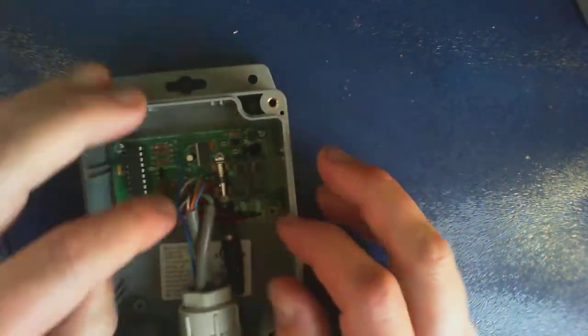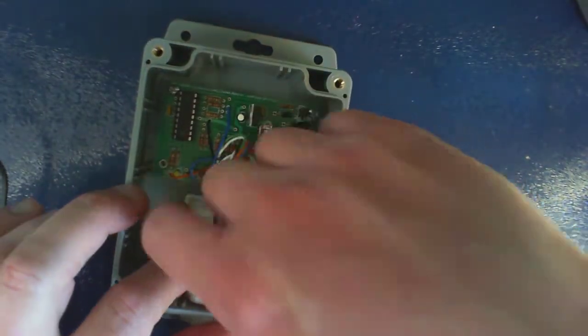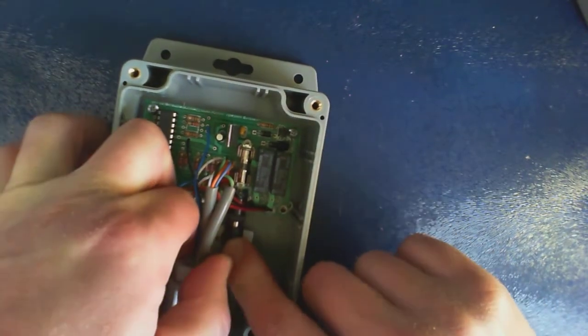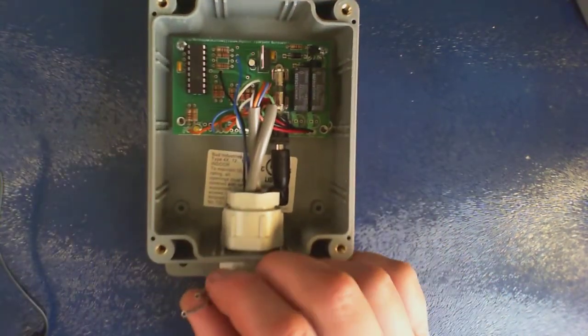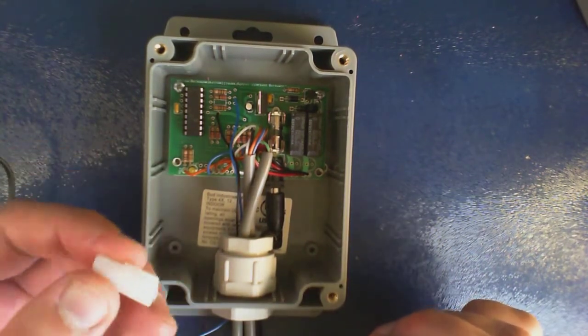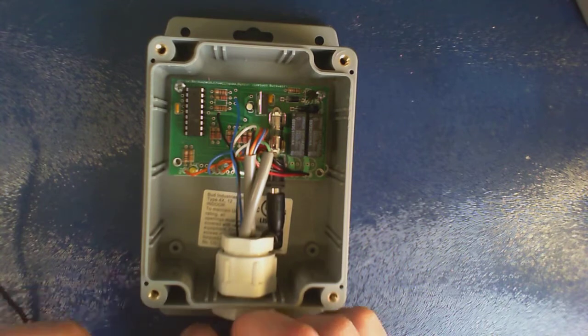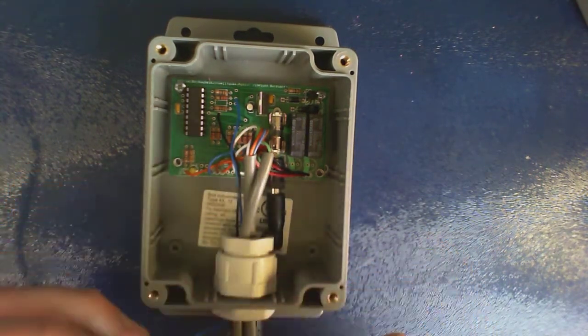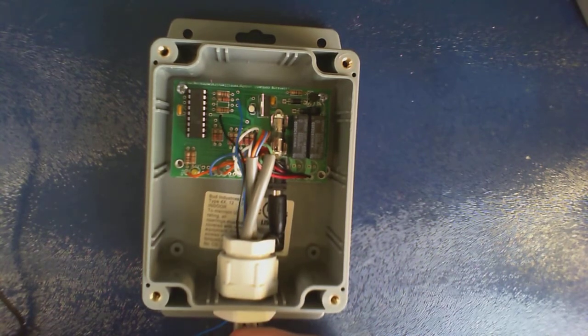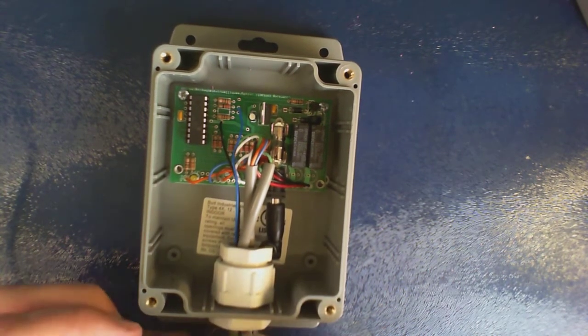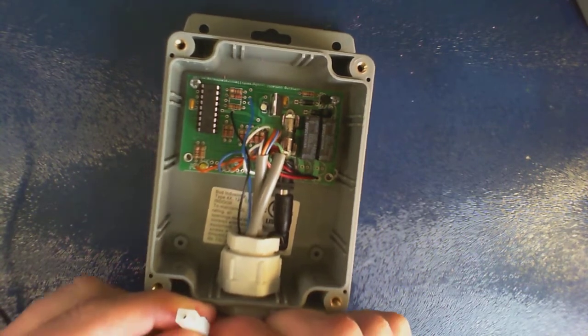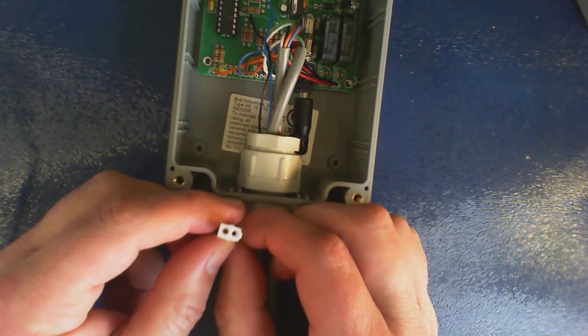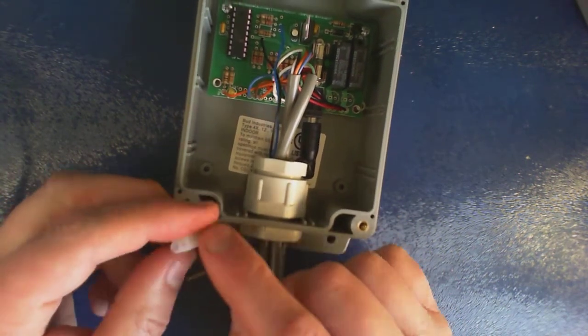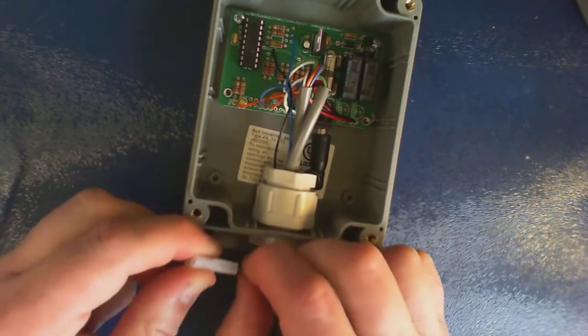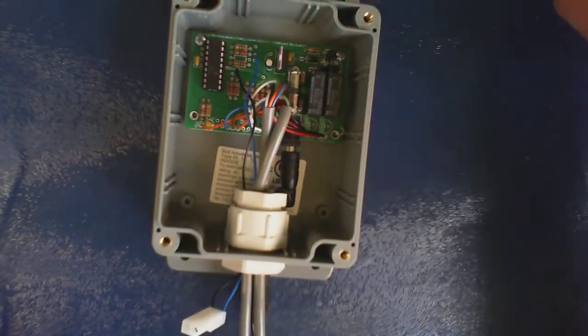All right, let's just double check, make sure we haven't snagged anything up here. So we've got the two new wires running through the cable gland. Cable gland is nice and tight. Power supply is locked in place underneath the cable gland. So I'm going to use one of these two position receptacles. I'm going to put the black into the square end, and there's a triangular end. The black into the square end, that's the ground. And then the transmit pin, we'll go into the triangular end there. So again, square end, triangular end, black in the square, transmit into the triangular end, and we'll put the lid back on.